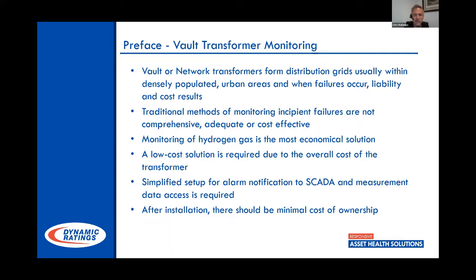So that was just some of our maintenance procedures where we would go in, and we would always make sure that we had positive pressure on these transformers to keep moisture out. We would typically do an oxygen analyzer to make sure that we had no oxygen present in the system. And then also we would take a TCG test, which I will go over in a further slide. A TCG test, for those of you that aren't familiar, was the precursor to our DGA testing.